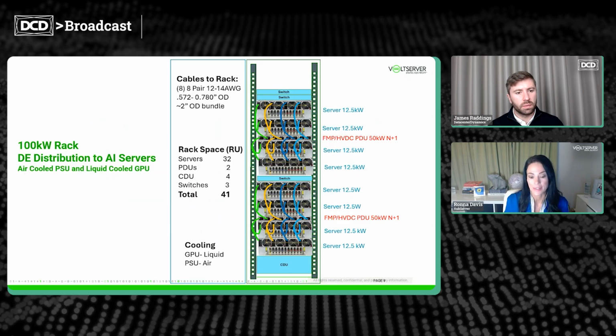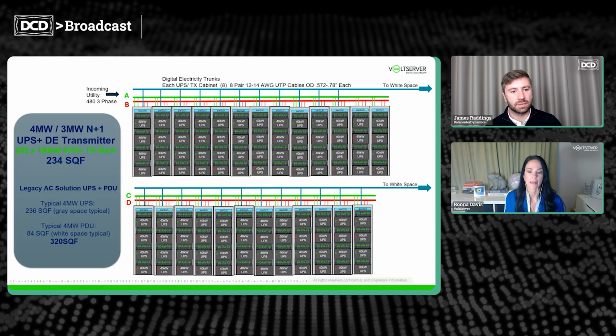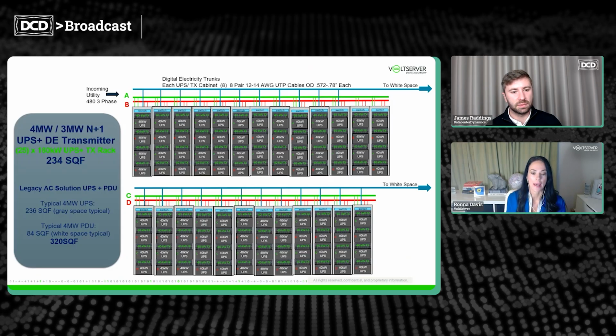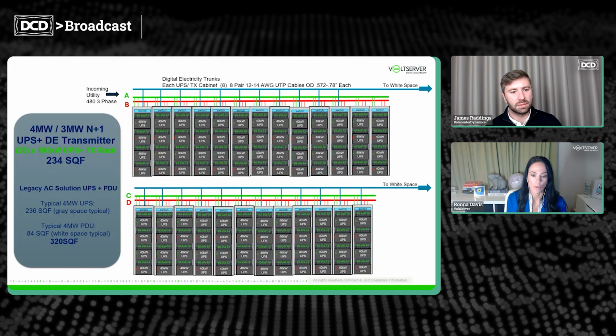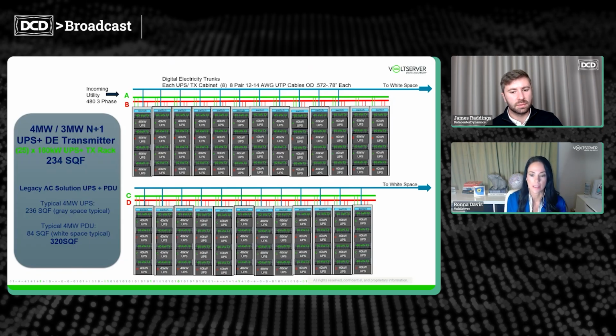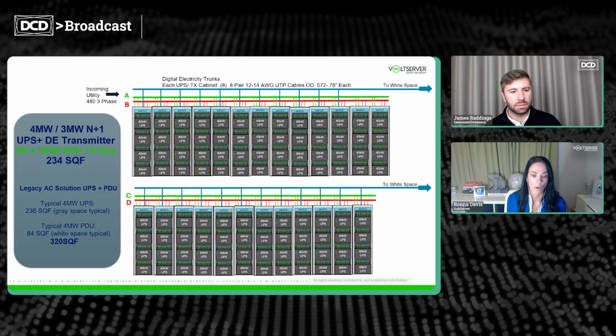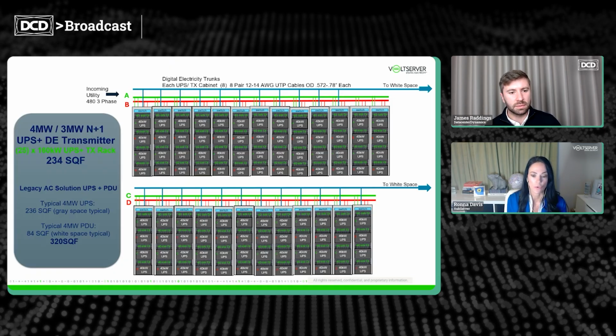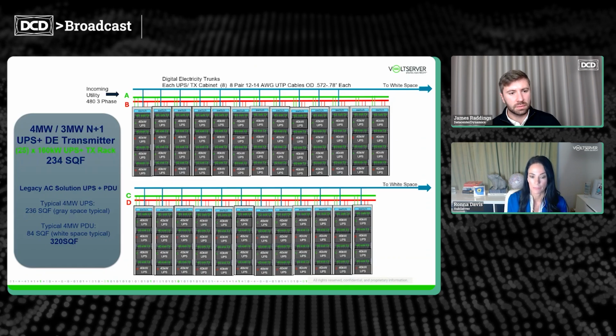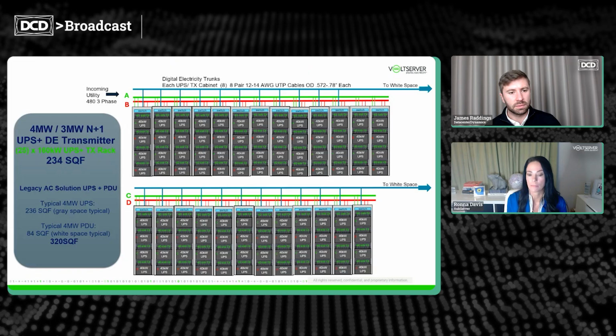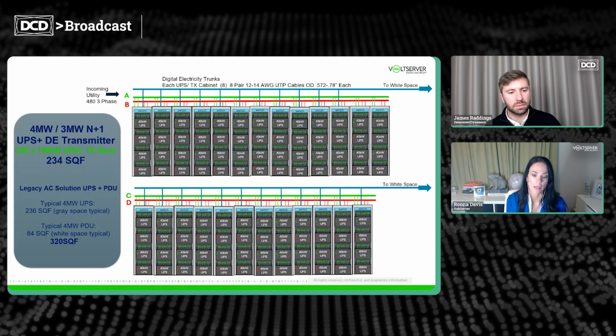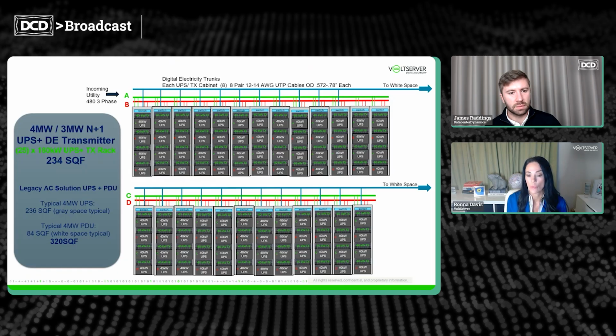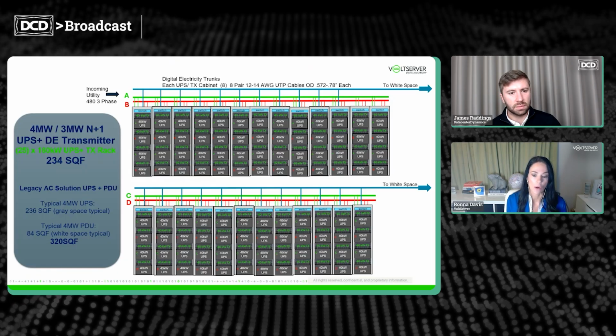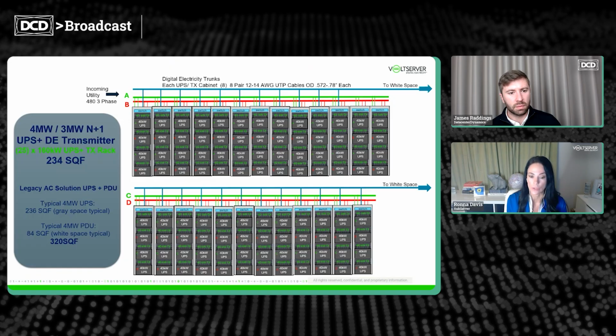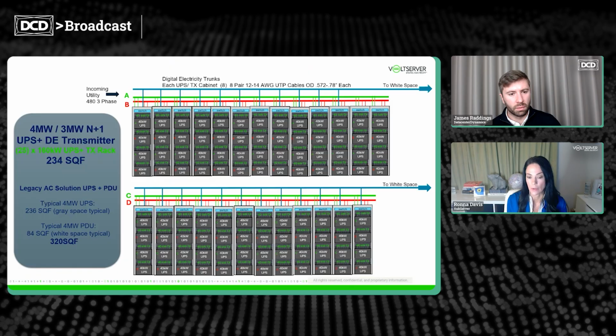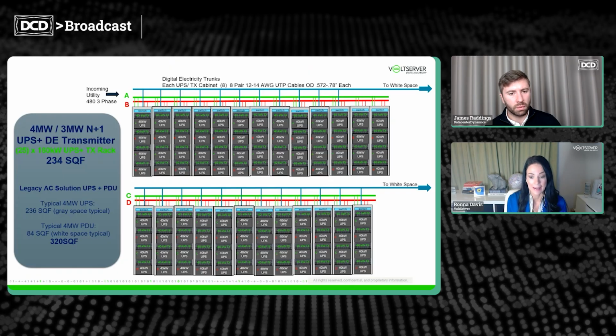Now we're going to pan back and look at the gray space in a 4 megawatt, 3 megawatt N+1 edge or enterprise data center. With digital electricity, we will accomplish this with 25 160 kilowatt UPS transmitter cabinets. This requires a square footprint of 234 square feet for both the UPS and the transmitter. Now, if you remember, the transmitter is equivalent to a floor PDU in a traditional lineup. In comparison, a 4 megawatt UPS in a traditional data center would require 236 square feet, and 4 megawatt of floor PDU will require an additional 84 square feet for a total of 320 square feet. It's pretty significant savings at scale.